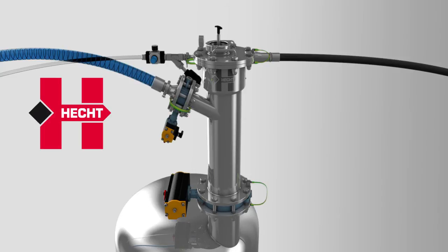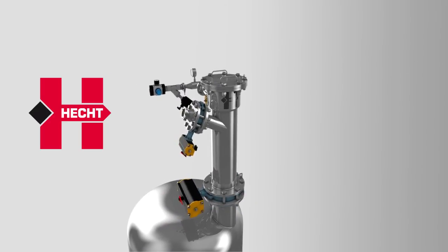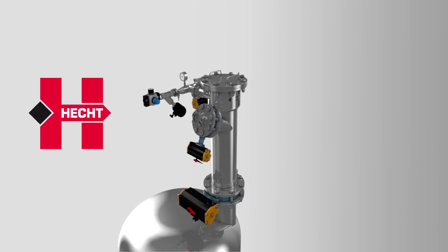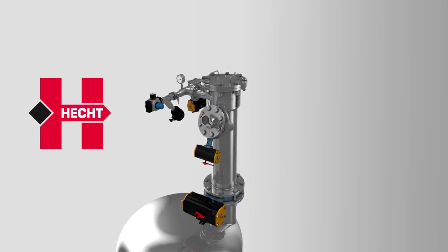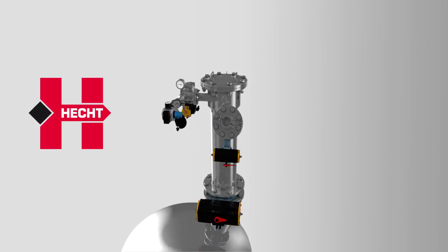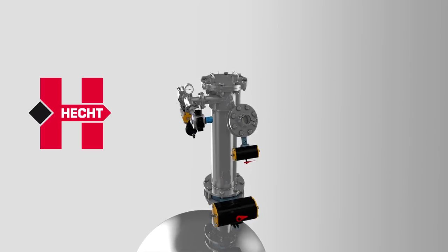When charging a vessel in an explosive or critical atmosphere, cleaning is also possible with nitrogen. Generally, products with a minimum ignition energy greater than 1 millijoule can be handled without problems. If the value is below that, the product data must be checked in greater detail and, if necessary, the product must be conveyed under inert conditions.